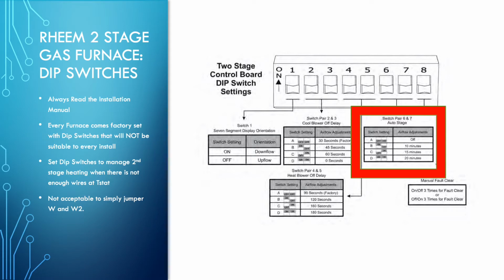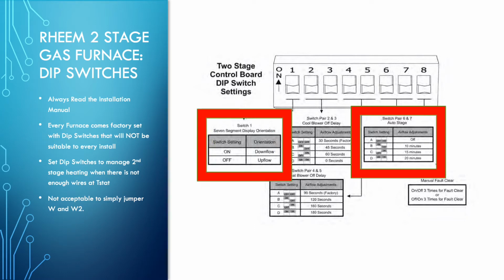So the furnace runs for 10 minutes in first stage, then after 10 minutes it steps up to second stage. Now, that's not the only thing you need to be paying attention to. This isn't even the only dip switch board in the furnace. There are others. You need to look at the configuration of the furnace that you're putting in. Now, when it comes from the factory, it's defaulted in the upflow position with the switch off. We put a lot of furnaces in that are in the downflow position, so you need to make sure you're configuring it for downflow. Now, this will adjust the blower settings a little bit when it's in the downflow, so it knows that it needs to run a little longer, but that can be controlled also.